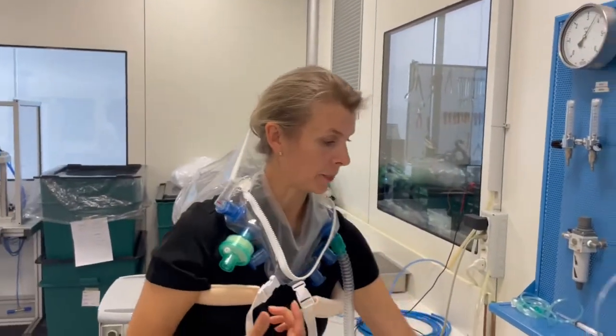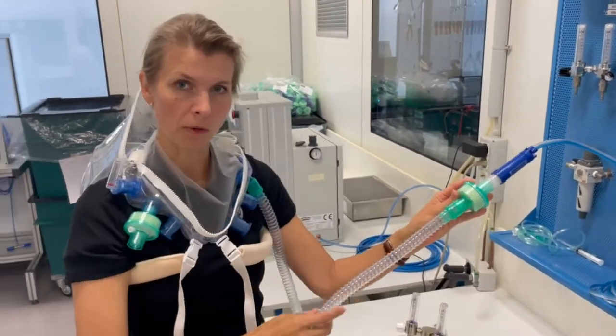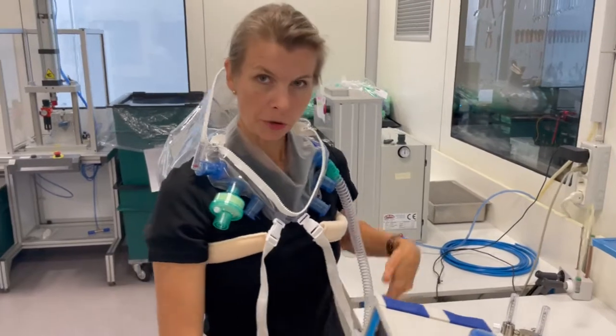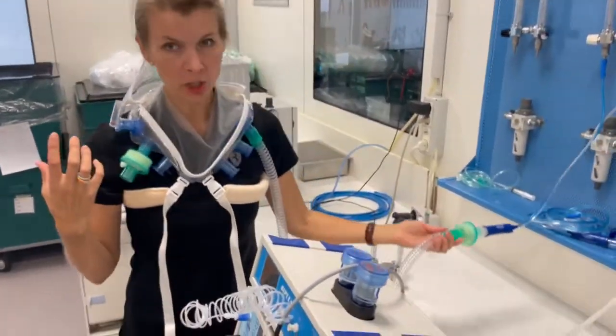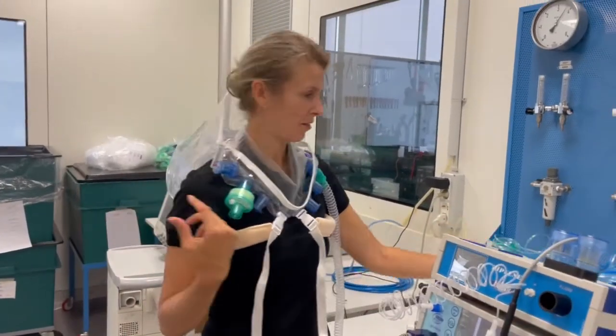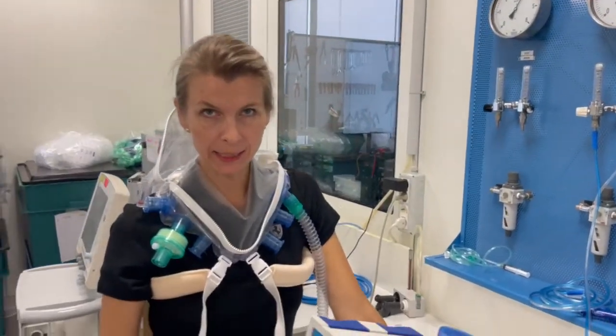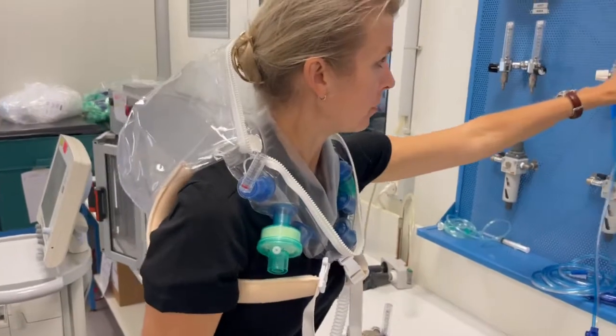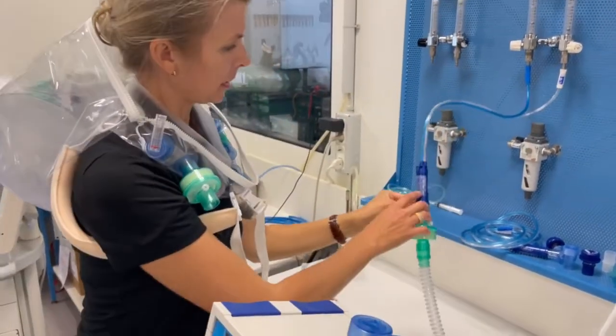I'm going to turn it on and it's going to be noisy because of the Venturi effect. The filter here reduces the noise going into the helmet — so the helmet doesn't make noise, it just amplifies it. You want a muffler for patient comfort — in this case, the filter. This is 10 liters per minute flow on a regulator, which will create 80 liters per minute flow in the helmet. Now we can change the oxygen based on a formula for the FiO2 you want — it can go up to 60%.